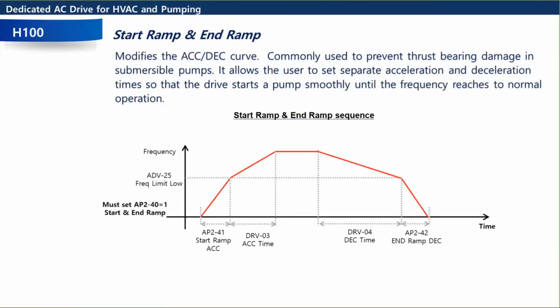And this is another pumping one. As I mentioned, there's a lot of pumping ones here. So start ramp and end ramp. This is good for submersibles, because submersible pumps have a thrust bearing in there, and that thrust bearing needs to get up to speed, typically 30 hertz within 1 second, so we can lubricate the bearings and not burn them out. If you have a very slow acceleration time on a submersible pump, it'll be okay, but it's not going to be okay for very long. You could damage those bearings.